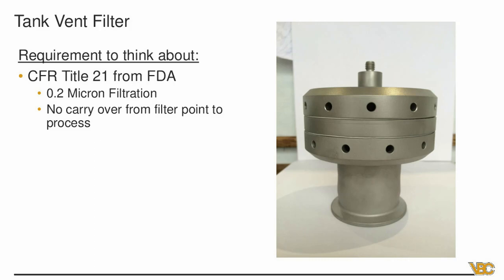Most of the filters on the market, including ours, have a way to be regenerated, whether it be an autoclave or steam in place or back flushing. There are a number of different ways that you can clean these filters to get you back to square one. Almost all the filtration manufacturers have it so you can regenerate a number of times. Our filters can be regenerated about 150 times. So if you're willing to invest in a cleaning cycle, it's a really good option to keep something for a long period of time and not have to be ordering spare parts all the time to replace what you have.